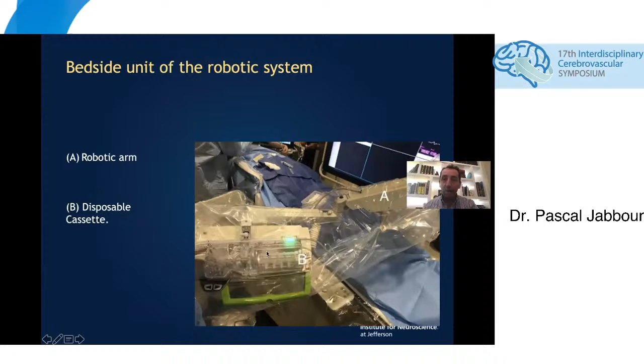B is the guide catheter rotation module. So you take the guide catheter with the 2-way needle, place it in B, and lock it. C is the guide support track. When you pull, this will go around your guide catheter, and this avoids any herniation when you're doing a translational movement. D is the device port, where you'll see there is a manual port and the regular device port. I'll show you once we open it.